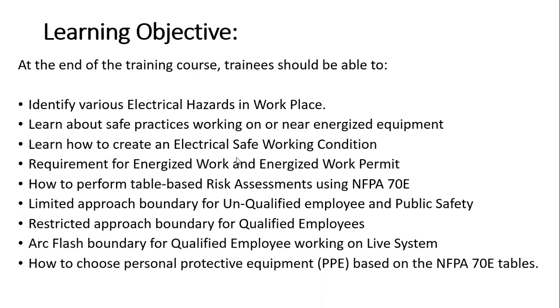You will learn how to create an electrical safe work condition, and about the requirement of the energized work permit. Most people don't know that beyond 50 volts you must have an energized work permit to perform any task, as per NFPA 70E. Below 50 volts, and if the source does not have enough capacity to cause a burn or arc flash, then energized work is permitted.